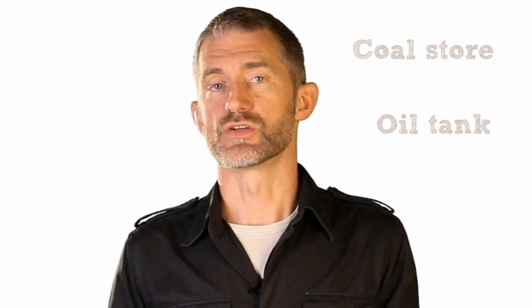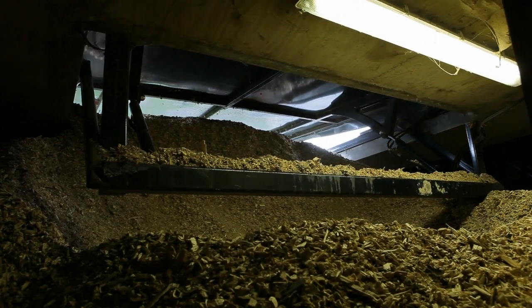In these situations, you'll need to investigate the potential to use the existing boiler room to house the biomass boiler. The space needed for a biomass boiler is not significantly different to coal or oil boilers, so in many cases, this will be feasible. Although substantially more space will be required if you're replacing a gas boiler system. If your existing boiler is coal or oil, you'll also already have a coal store or oil tank, which may be a suitable location for the wood fuel store. It's likely to have to be enlarged, as wood chip takes up more space than either of these fuel types.